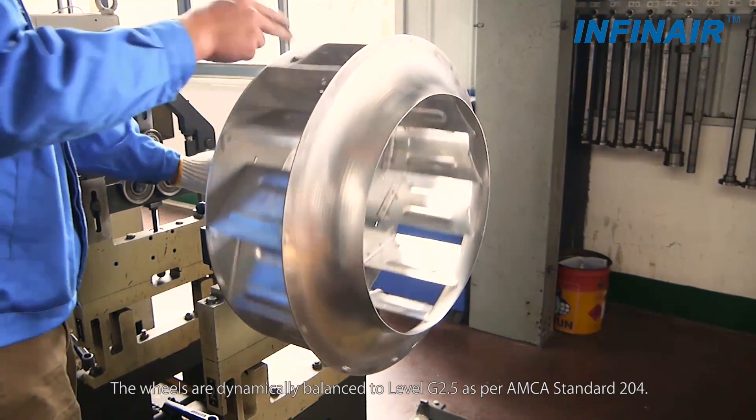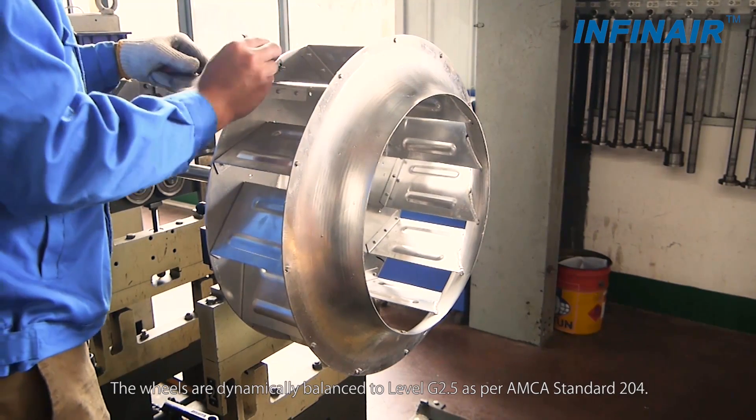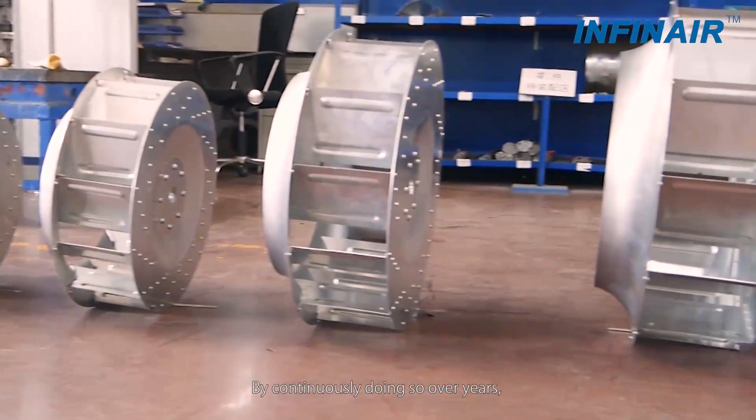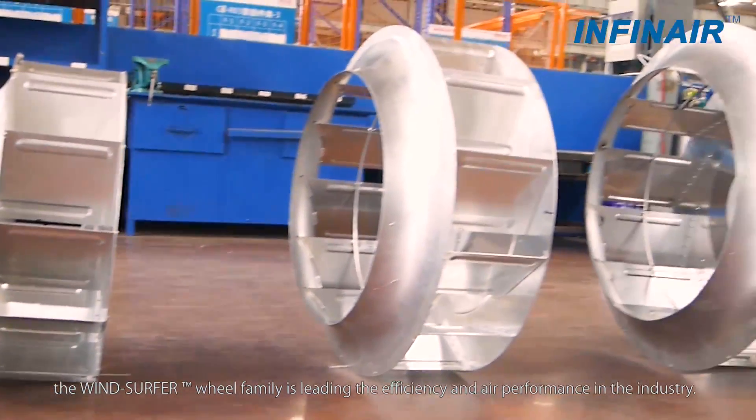The wheels are dynamically balanced to level G2.5 as per AMCA Standard 204. By continuously doing so over years, the windsurfer wheel family is leading the efficiency and air performance in the industry.